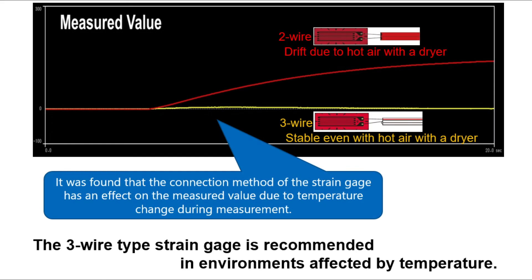The three-wire circuit, as you can see, compensates the change very well, showing that this circuit configuration should be used for most applications where the wire is longer than one meter or there is a risk of differential temperatures.